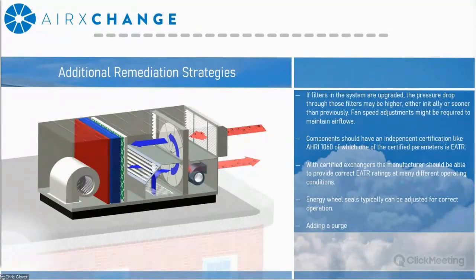So if you're evaluating a unit that's AHRI 1060 certified, you may use those ratings in addition to the site recorded pressures to determine what the relative leakage is. Most energy recovery devices, as I mentioned before, do have a seal system that's adjustable, so you can maintain it over time. You just need to adjust it or replace it depending upon the manufacturer's recommended instructions.